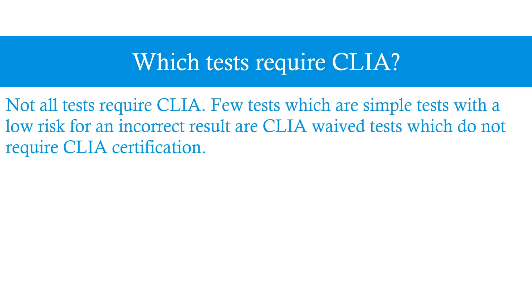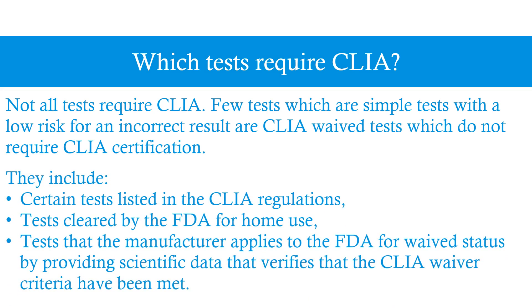Not all tests require CLIA. Few tests which are simple tests with a low risk for an incorrect result are CLIA-waived tests, which do not require CLIA certification. They include certain tests listed in the CLIA regulations, tests cleared by the FDA for home use, and tests that the manufacturer applies to the FDA for waived status by providing scientific data that verifies that the CLIA waiver criteria have been met.